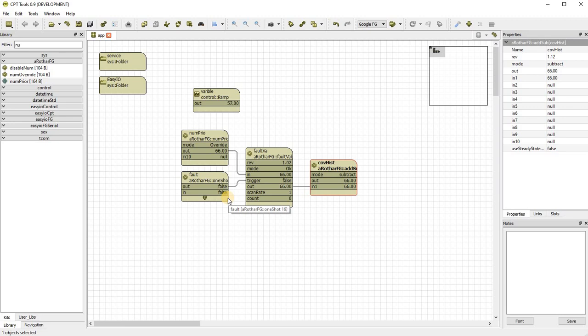Because sometimes it's what happens leading up that is causing the problem, not what happens at the time of the event. Because we've found that with chillers or other things like that, the fault signal can come through seconds after the equipment has stopped. So the fault can be delayed. So this can be used to compensate for that so you can actually get real-time values of when the unit stops.